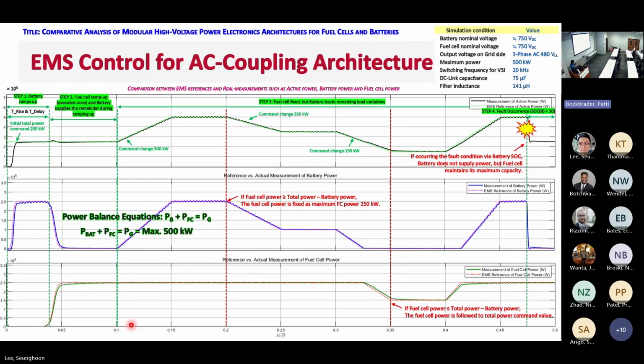Step 3: the fuel cell power becomes fixed and the battery follows the remaining load variations. As shown in the graph, whenever the load increases, the battery power rises, and when the load decreases, the battery output is reduced. EMS ensures that the fuel cell never exceeds its maximum rating of 250 kilowatts.